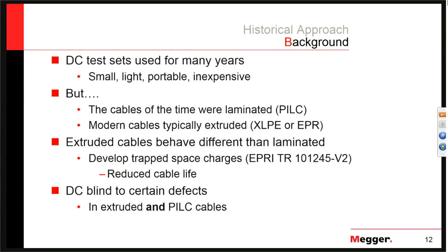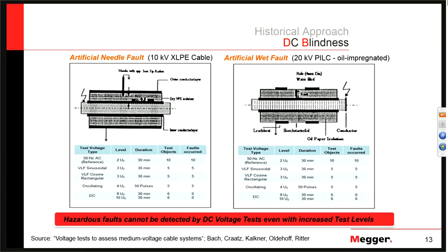DC is also blind to certain defects in both extruded cables and PILC cables. Researchers published a paper where they drove a needle partway through the insulation and grounded it — not a complete short, but a severe defect by any definition. What they found was that AC was 100% effective at finding this fault and DC was 0%. Not only was DC ineffective, it failed to find the fault even at much higher voltages — 8 to 10 times operating voltage — compared to AC finding it at about 3 times operating voltage.